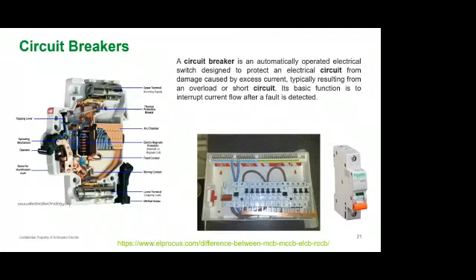So what I told about a bimetallic strip is this one, thermal protection bimetallic. So this will be always in contact here when the switch is on. When the current is exceeding, it gets heated and starts to bend, and it starts to disconnect from this area, so that power supply will not flow from the connection point to distribution point. And that's how an MCB works.